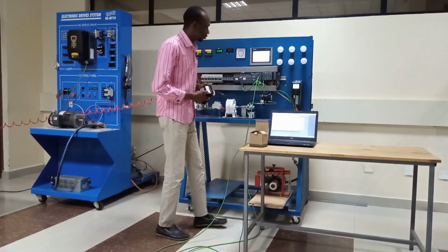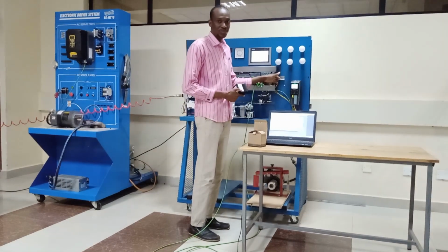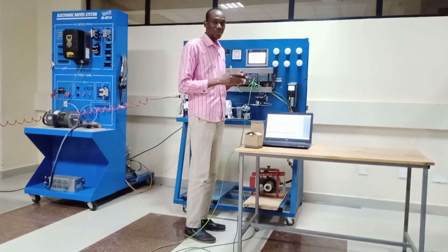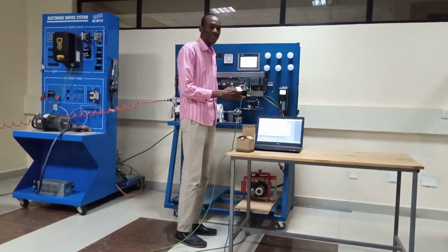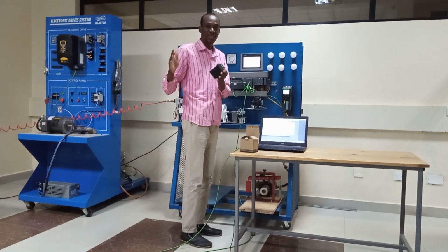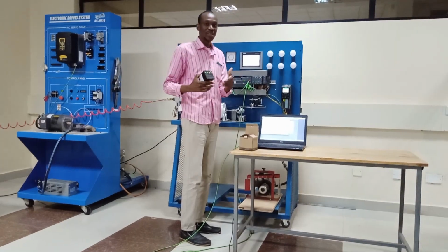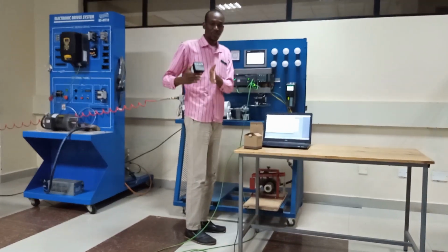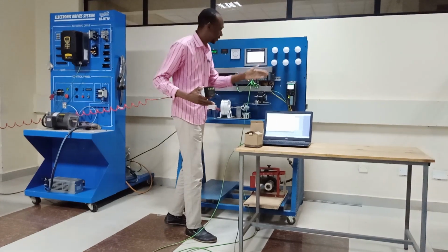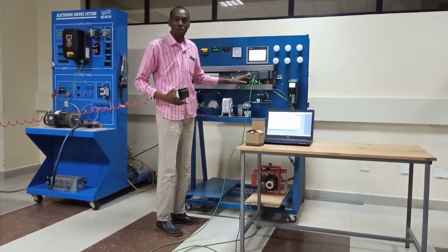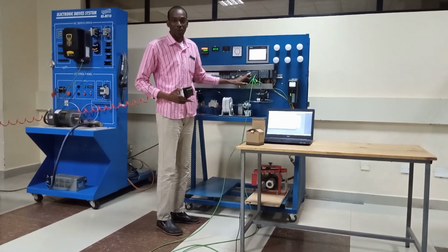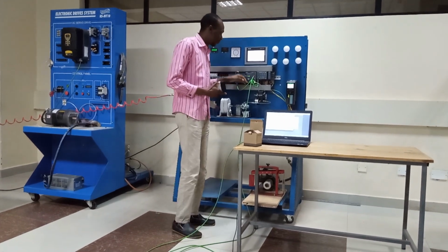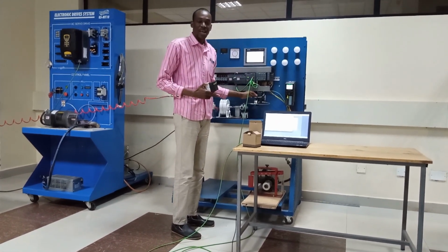The next step is to set your transducer. Then you have zero and span. Setting this transmitter means that you are setting the range of your analog output signal. The input is voltage. Then it will convert the input voltage to output current from 4 to 20 milliamps. And this signal is taken to the analog input/output module of your PLC. And from here, the output has to go to the IP converter.